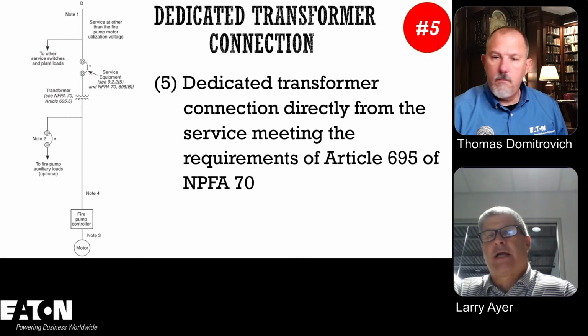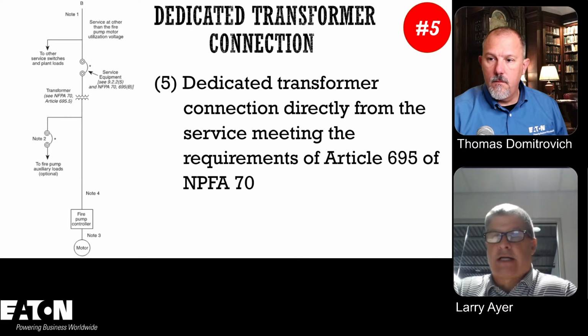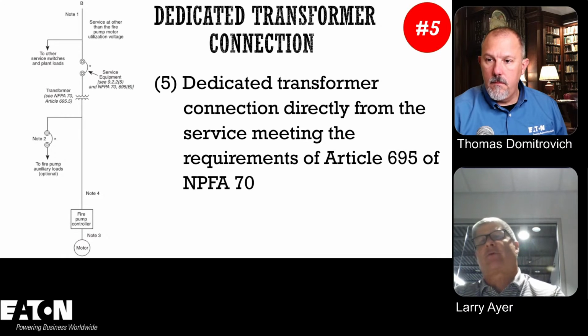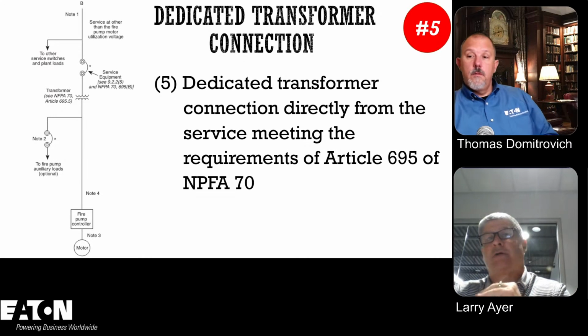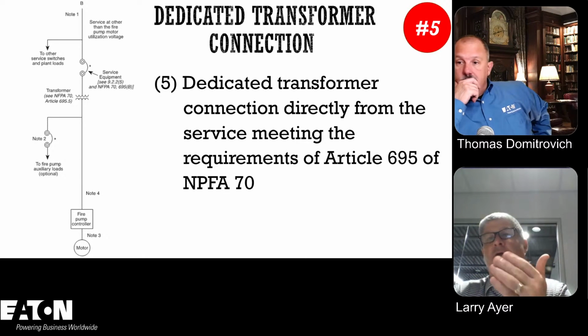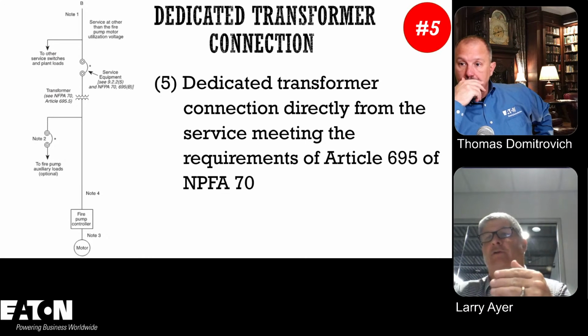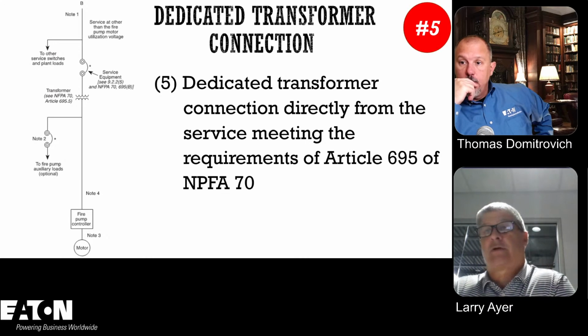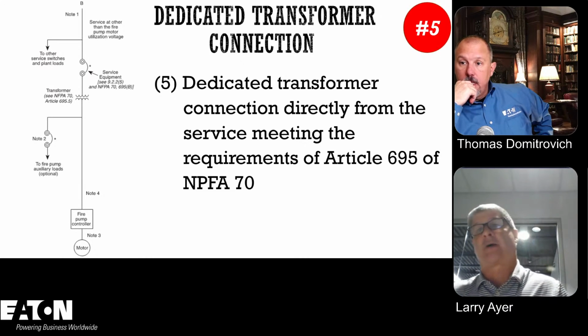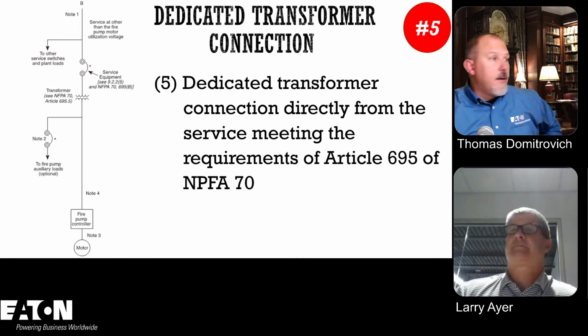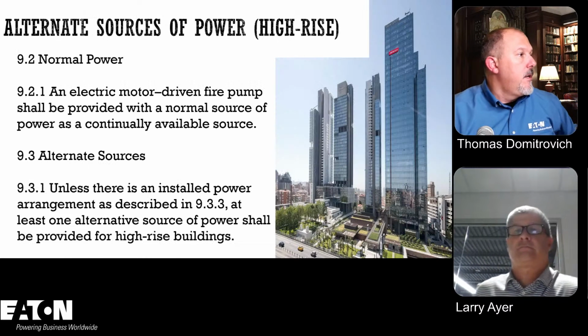Excellent. We had this right now. We're retrofitting one in downtown Cincinnati. Originally, we had a 208 volt service, and we had a 480 volt fire pump, so we stepped it up. And when they put the new fire pump in, and we'll go over the voltage drop issue in a little bit, we got rid of the transformer, basically because of the voltage drop. Interesting. Okay. All right.